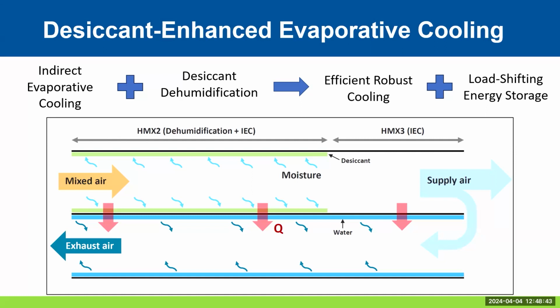But the benefit is that it can still provide cooling even if it gets really humid. And so if you just have a few hours a year that get really humid, this could be great. Or if you want to load shift, even in Miami, you can choose to do the desiccant regeneration whenever you have excess renewables, and you can just use that stored dry desiccant to provide cooling when you don't have excess renewables. But that load shift capability is primarily in humid environments.